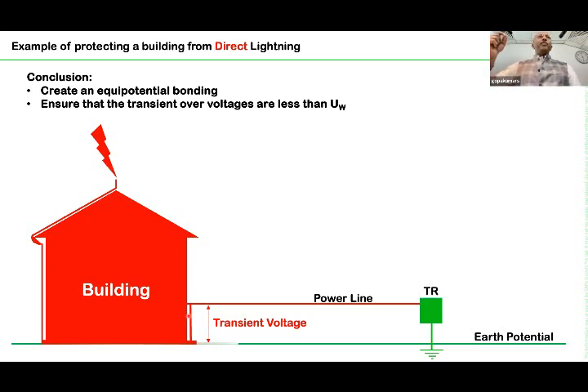Before asking this question, you should think: what will happen if there is no SPD in your building? If there is no SPD here at the service entrance, spark over will happen, failure will happen, and the current will pass through the same route. Anyway, the current is going to flow through the power line. The question is, without an SPD, it will destroy your distribution board and flow. With an SPD, your distribution board is protected and it will flow. That is the only difference.